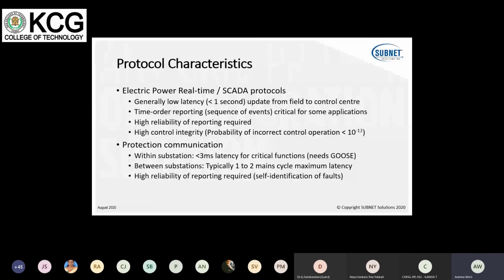Protection communications within the substation, this is where GOOSE operates and does the wonderful thing that nothing else can do. It has very short latency between protection devices. Between substations, we can typically operate in about 1 or 2 mains cycles, something in the order of 20 to 50 milliseconds. These systems also need high reliability and self-monitoring to identify if they have failures.